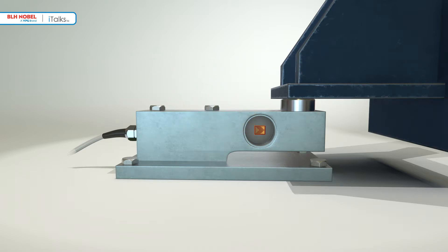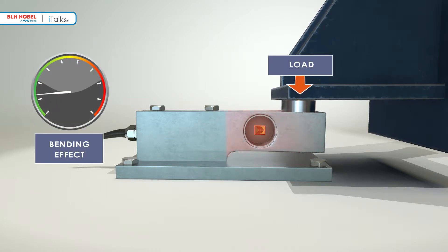In a simple shear beam, there are also bending strains present, which contribute to the output. Under laboratory conditions, the bending effects though present are small in comparison to the applied load and thus do not adversely affect the accuracy of the load cell.